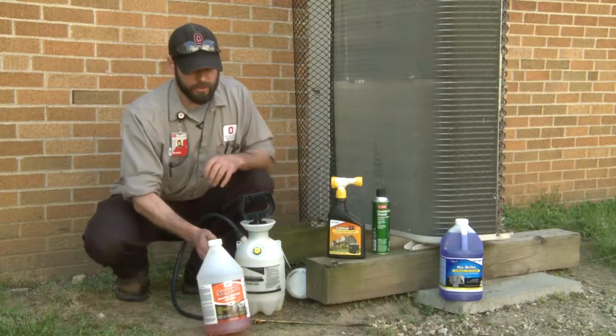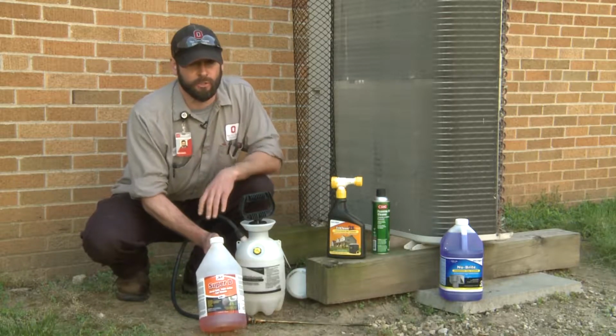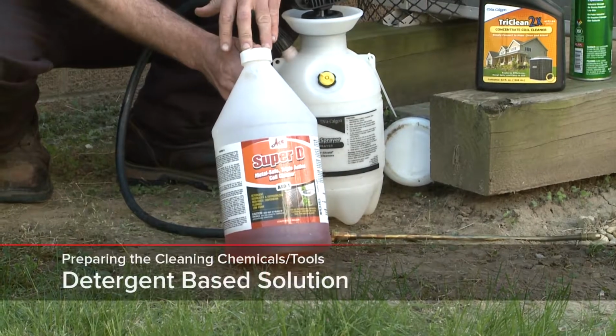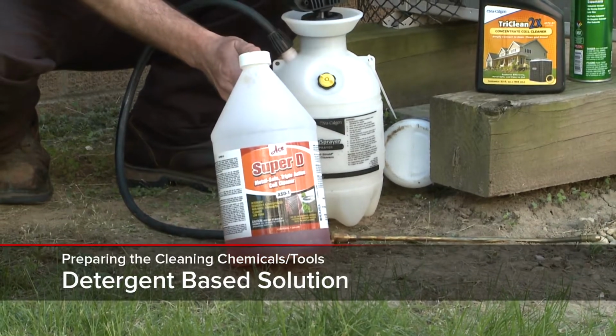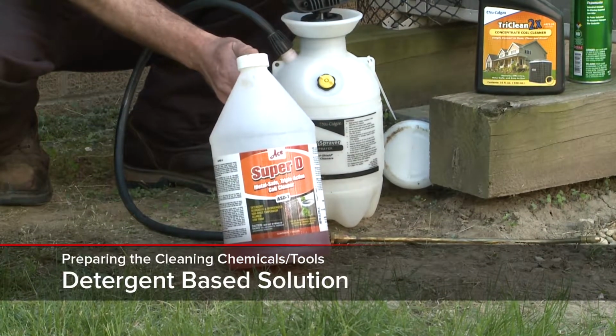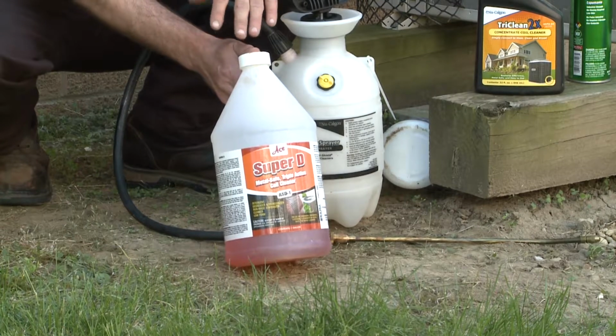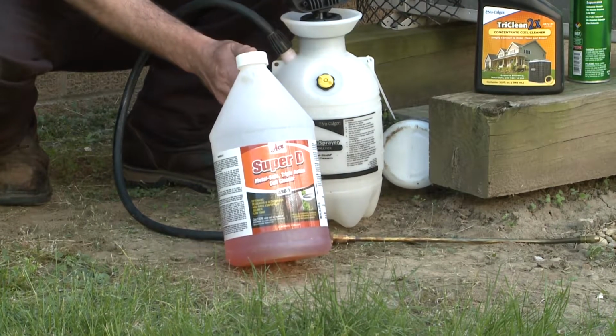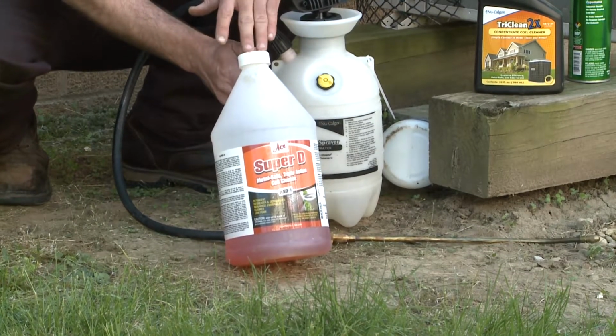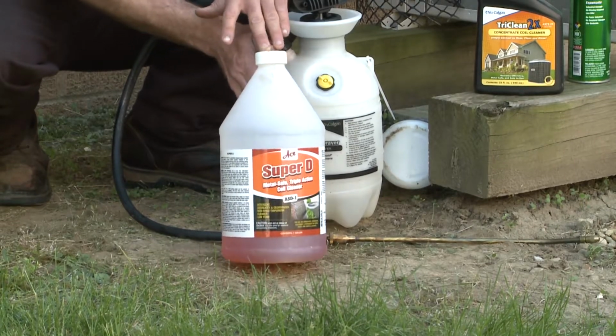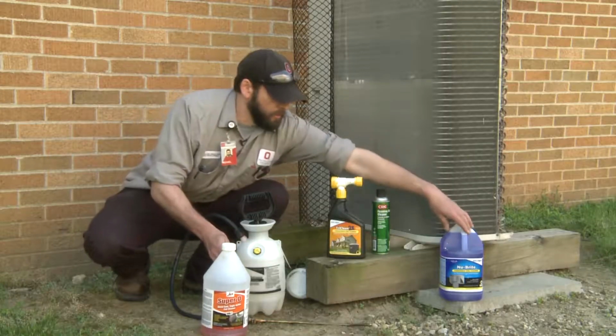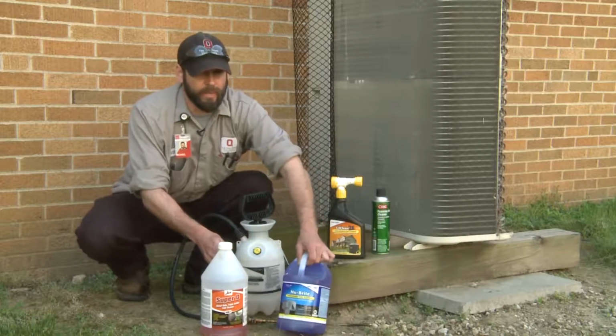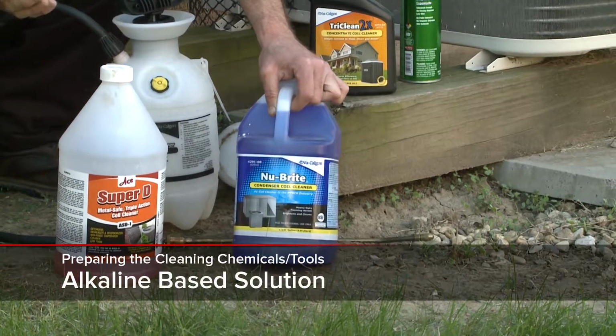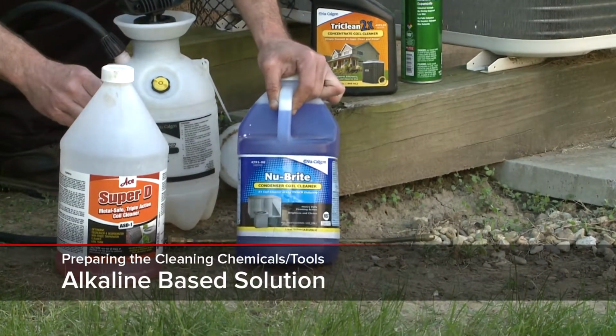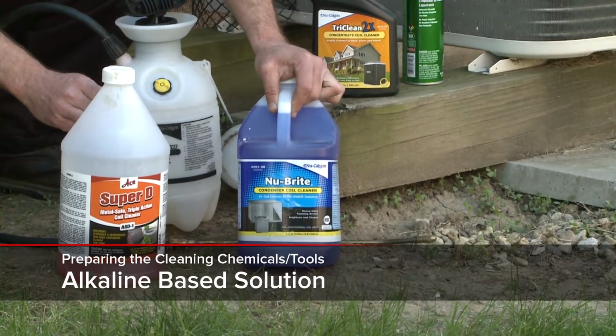The two types of solution that you'll typically use are a detergent-based solution, which would typically be used on air handler coils, chilled water, preheat coils, even reheats. The reason you're going to use that detergent, and also on your evaporators, is because that air is going to be exposed to humans.